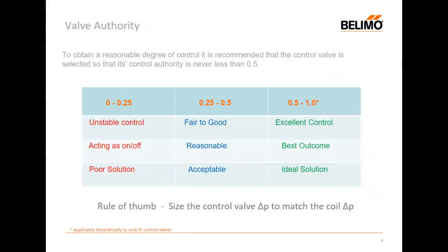When we take a closer look at valve authority, I've split it into three possibilities: 0 to 0.25, 0.25 to 0.5, and then 0.5 and upwards, maybe to 1. If we look first at a poorly selected control valve with little pressure drop across it in relation to the circuit, we're going to have to settle for unstable control. Anything below 0.25 generally is acting in on-off, so it's no longer modulating. We should not have wasted our money buying a modulating actuator and a modulating valve if it's going to behave in this way, and that really is regarded as a poor solution.